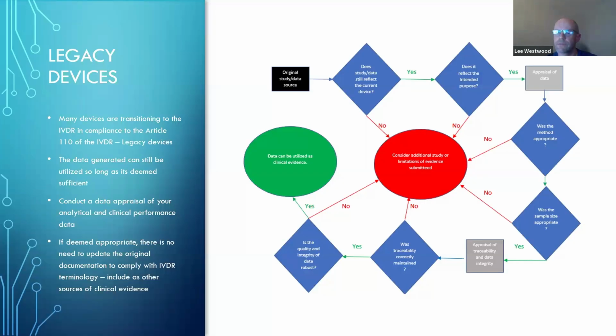Legacy data devices I've kind of spoken about already. Okay, so for your analytical performance and your clinical performance, I've developed this flow chart, which is based on something that MedTech put together for published experience gained. But essentially, you want to check that the data that you've generated for your legacy device is still reflective of the device you're putting through the IVDR. Was it done using a suitable method, a state-of-the-art method? Was there enough samples used?